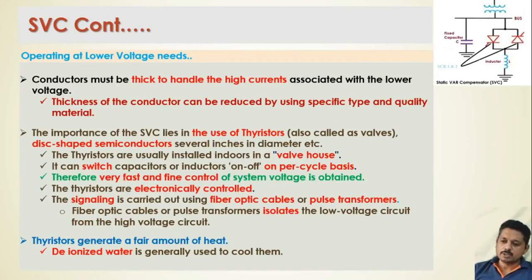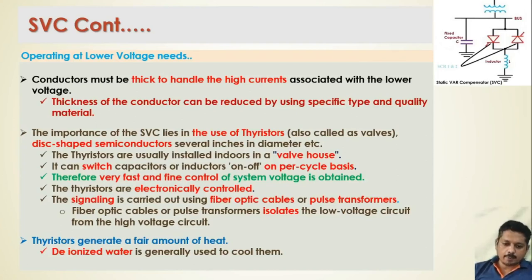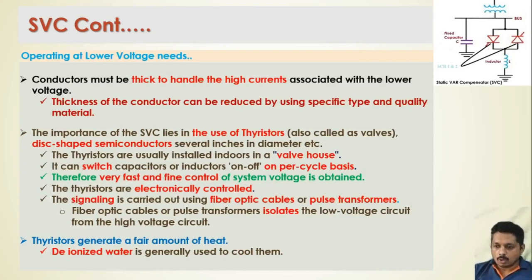To reduce the size of conductors, thyristors are very important in our SVC. Thyristors are also called valves because they perform switching. They are disc-shaped semiconductors, several inches in diameter, installed in valve assemblies. These valves or thyristors can switch capacitors or inductors on a per-cycle basis, depending on whether the system demands reactive power absorption or delivery.